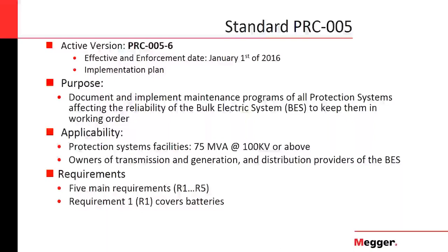Going into the details of the standard, as I said, the standard is called PRC 005. It has passed through several versions or revisions. The one that is enforced and is current or effective right now is PRC 005-6. The previous one was PRC-005-2, but that was superseded by this one about a year ago. The purpose of this standard is to ask electrical companies to document and implement a maintenance program for all of the protection systems that will have an effect on the reliability of the bulk electric system, with the purpose of keeping them in working order.